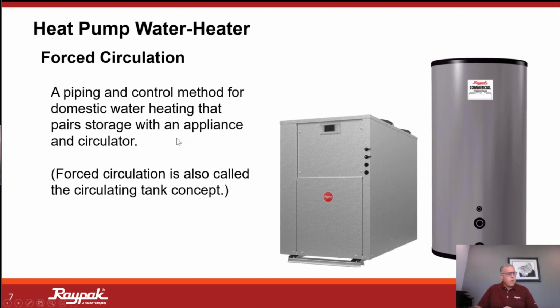So we know that forced circulation, it's also called the circulating tank concept, we have a very low mass heater, very low water content, and we need to harness those BTUs, or rather harvest those BTUs, and place them into that storage tank. So that's what we're going to talk about. We're going to have a circulator. We're going to take that heat we're securing out of the ambient air, and we're going to place it into that storage tank for domestic use.